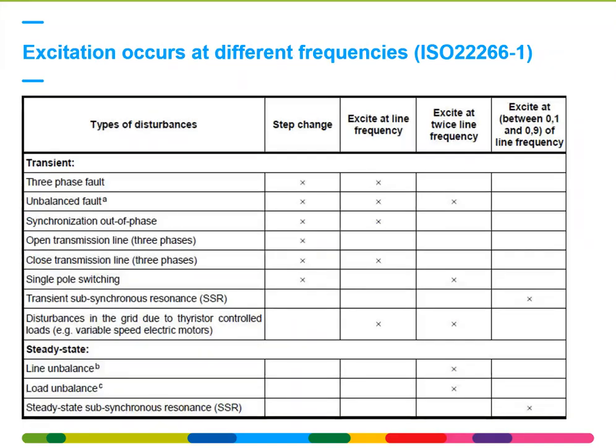The ISO standard gives an overview of different excitation disturbances on the grid. So you can see they're subdivided in transient and steady state ones. And on the top horizontal bar, you can see the effect it has on the machine. So the type of disturbance can be a step change. It can excite at line frequency, twice line frequency, or anywhere in between 0.1 and 0.9 of line frequency. The norm is, well, there is a good guideline on line and twice line frequency, and by design, typically the OEM ensures that there are no torsional natural frequencies close to once and twice line frequency.